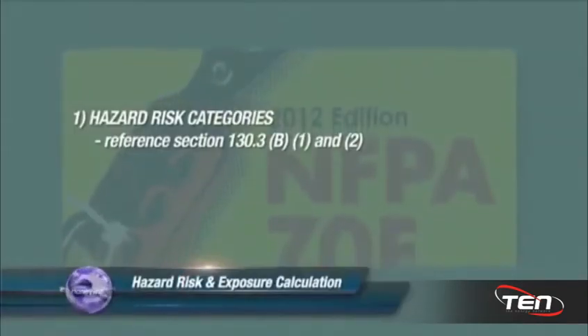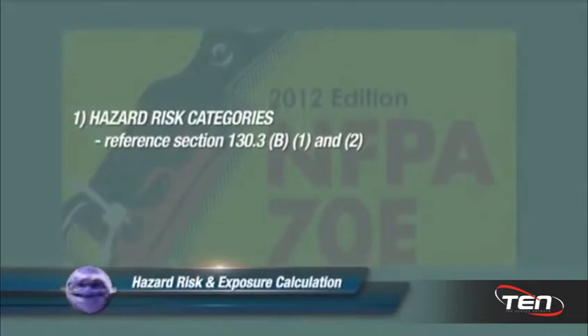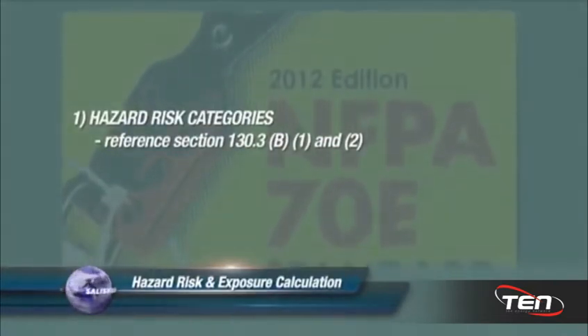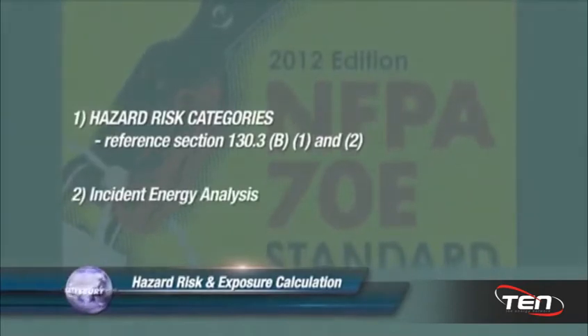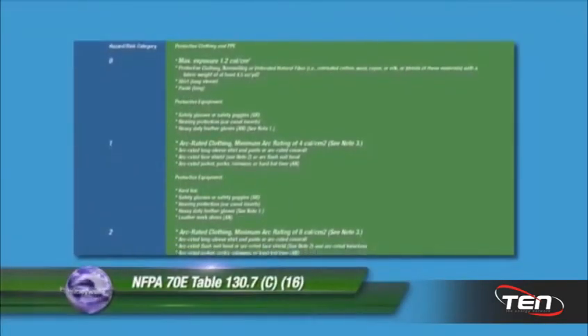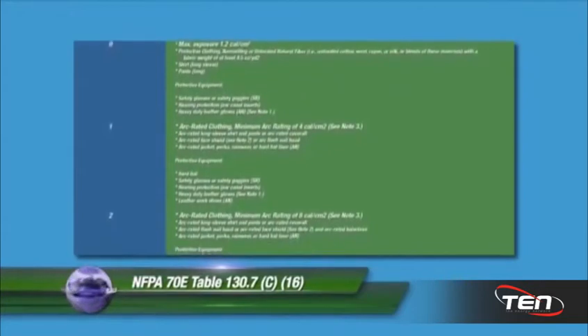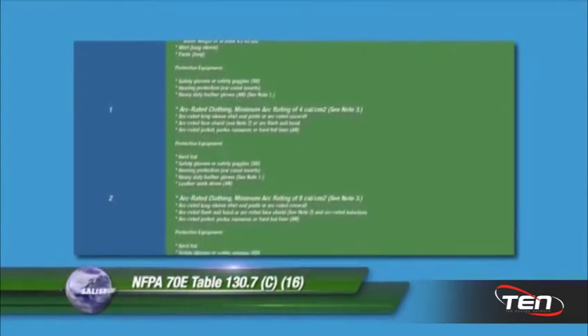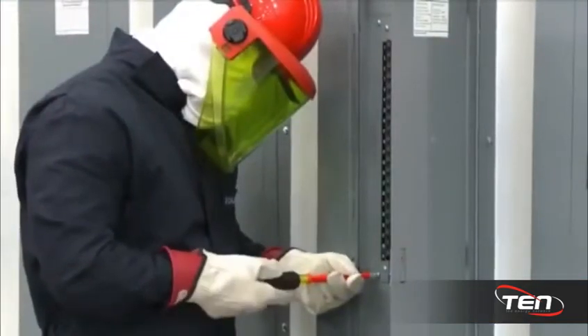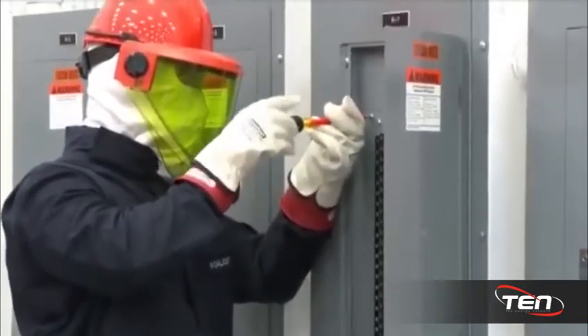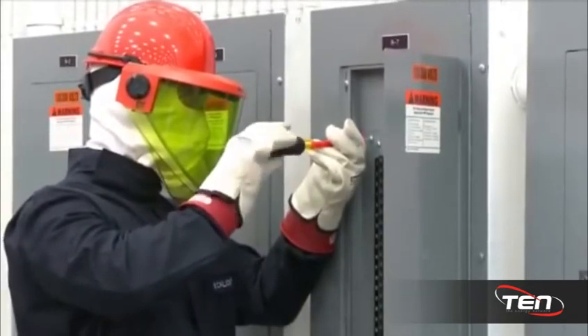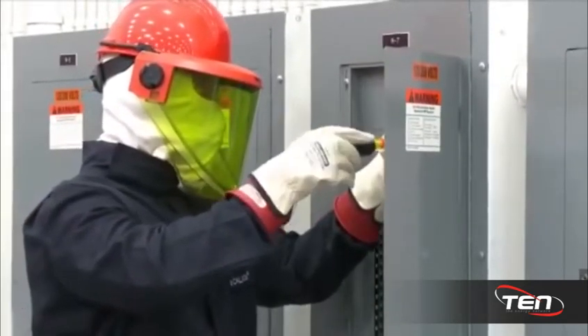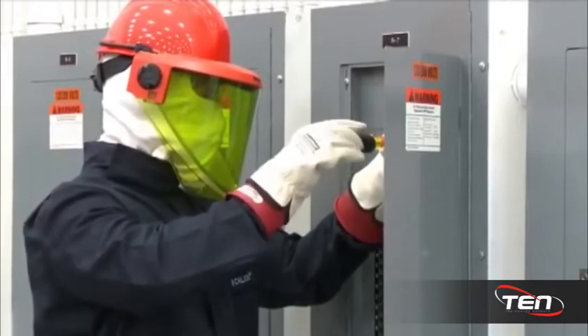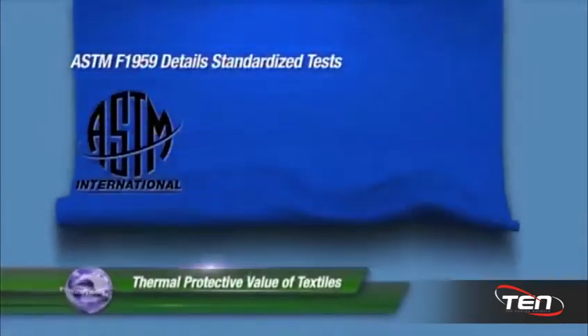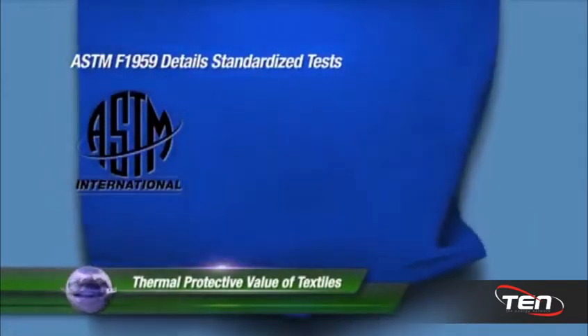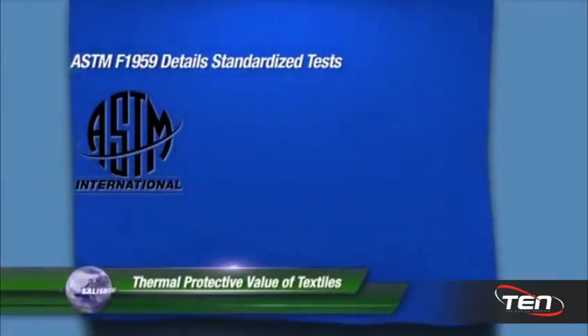First, hazard risk categories, reference 130.3, sections B, 1, and 2. And secondly, incident energy analysis. NFPA 70E has clearly defined hazard risk categories or arc flash ratings that help to determine the clothing needed to keep safe in different conditions. To determine the hazard risk category or arc rating, NFPA 70E requires an incident energy analysis of the job to be performed. Each situation is unique and needs to be evaluated. ASTM F1959 details the standardized test that must be used to determine the thermal protective value of textiles in an electrical arc application.